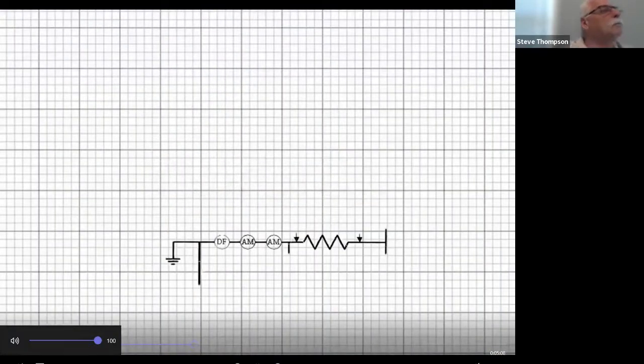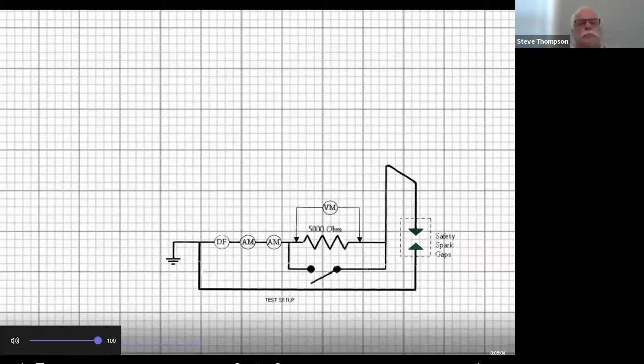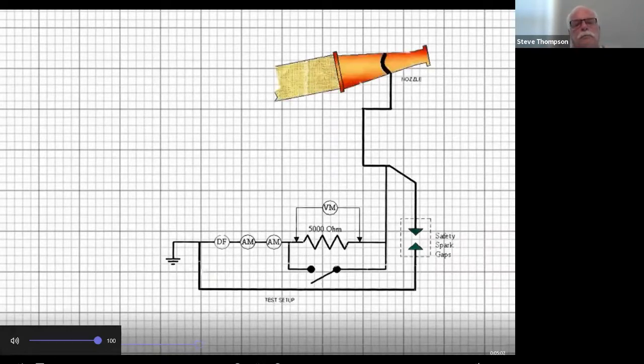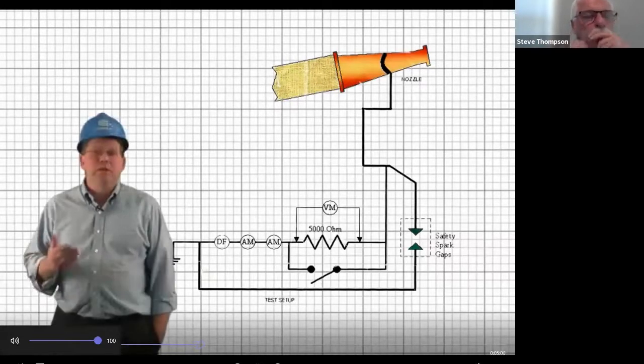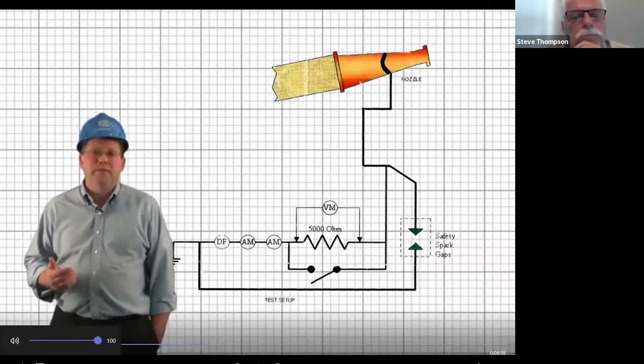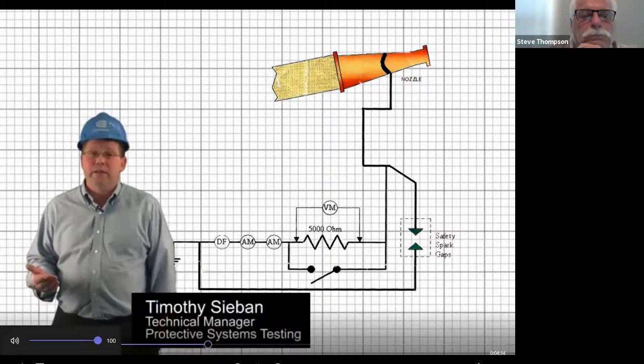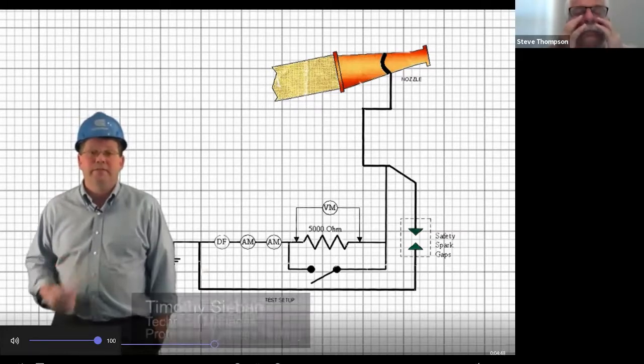For this test, it was my task to come up with the circuitry and equipment. With the field technicians, we connected up the equipment so that we could determine which distances were safe to spray the F500 concentrate and water mixture on live bus. My name is Tim Sieben, and I'm a technical manager for protective systems testing here at Con Edison Substation Department.